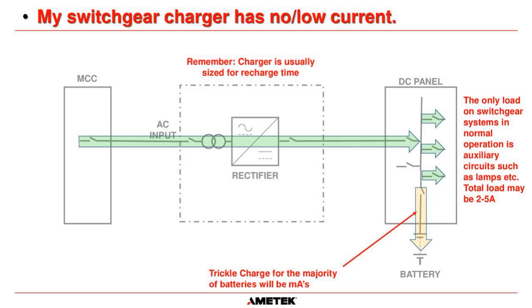What's this one here? My switchgear charger has no low current. Oh, a very popular misconception. A lot of charger manufacturers, and I think we have the option as well, let you get an alarm on your charger for low current situations. Because most people say, okay, if I have no current on my charger, then there's something wrong with it. And that's not necessarily the case. Let's say that this is set at 0.5 amps. And remember, well, not remember, but know that measuring very small amounts of current is very, very difficult because we're talking about millivolt sources that convert the amps into millivolts, and we have to compare that against a reference signal. It's very, very difficult. So really anywhere below 5 amps, it's very difficult to measure accurately.